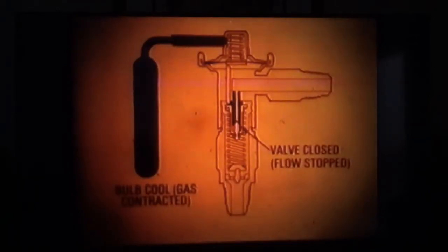As this temperature increases, the gas in the bulb is heated and expands, raising the pressure above the diaphragm in the expansion valve. The increased pressure opens the metering valve, allowing more refrigerant to enter the evaporator. When the temperature of the refrigerant leaving the evaporator drops, the gas in the sensing bulb contracts, reducing pressure on the diaphragm. This allows the metering valve to reduce the flow of refrigerant to the evaporator.